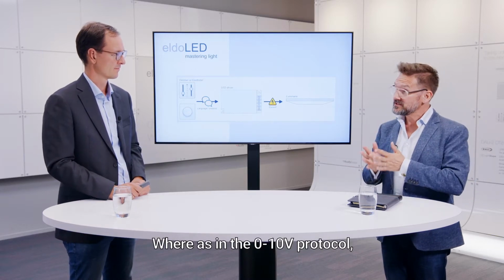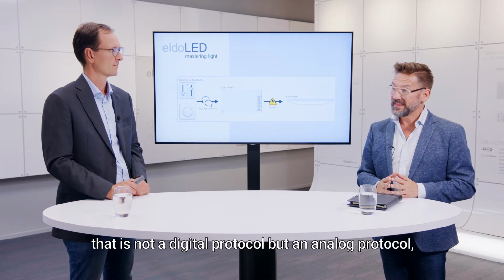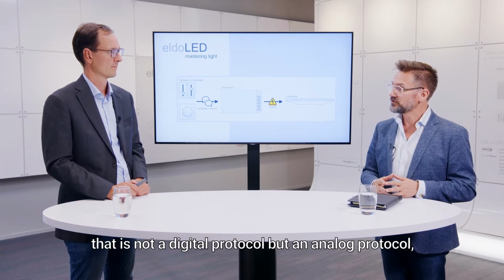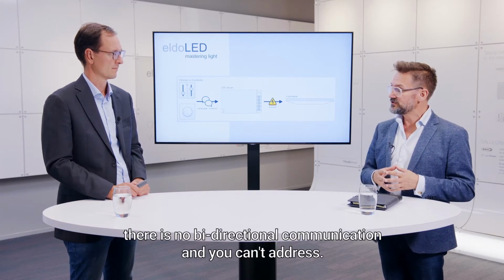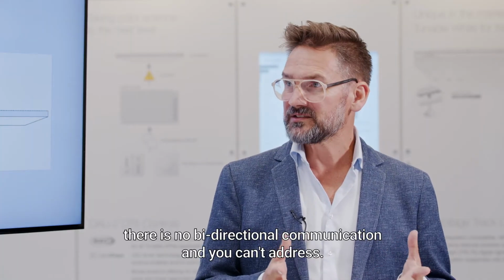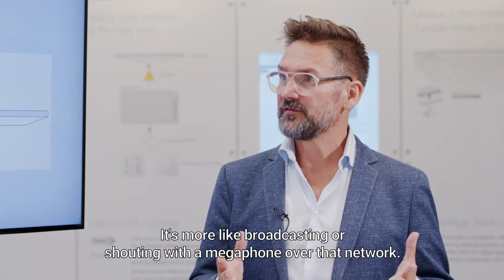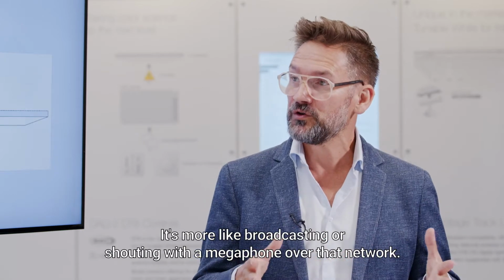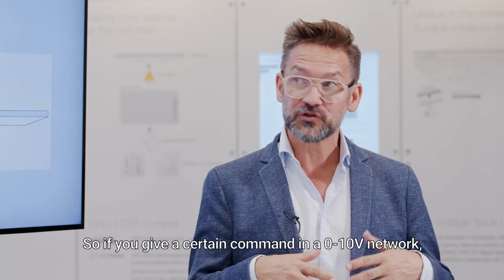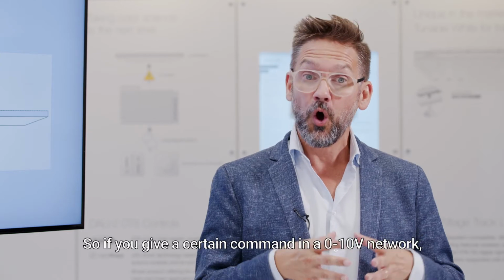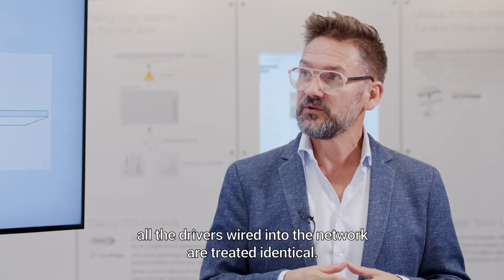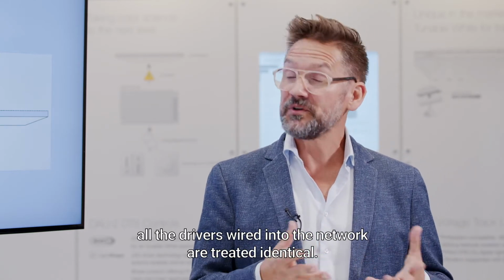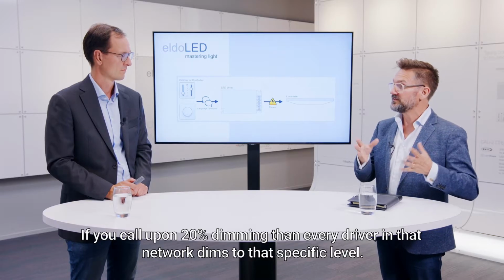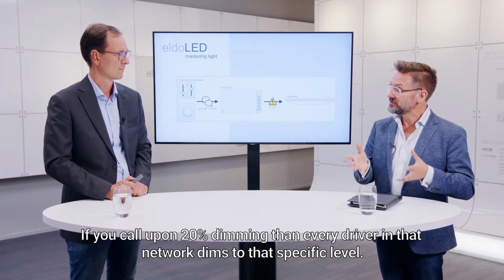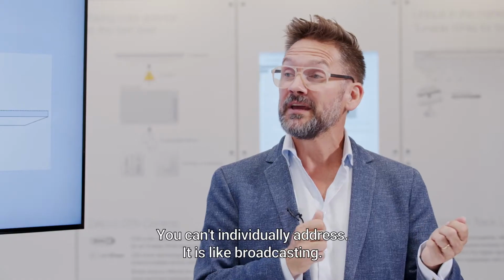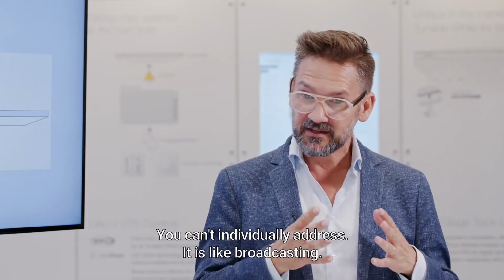Whereas the 0 to 10 protocol is not a digital protocol but an analog protocol. There's no bidirectional communication and you can't address. It's like broadcasting, if you wish. It's like shouting with a megaphone over that network. So if you give a certain command into a 0 to 10 network, all the drivers wired into that network are treated identical. If you call upon 20% dimming, then every driver in that network dims to that specific level. You can't individually address. It's like broadcasting.